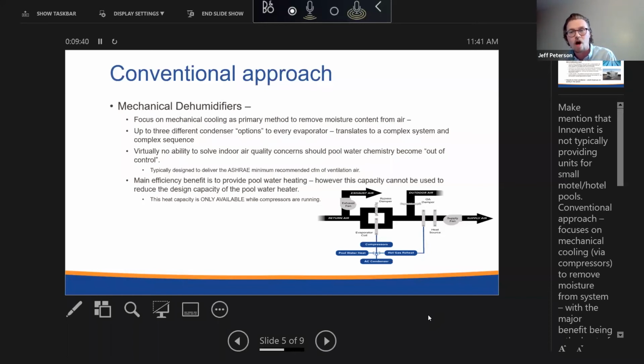The single biggest drawback to this approach, though, is it only allows for the minimum ASHRAE prescribed amount of outside air. So if you have a situation where chloramines build up in the space, and that's not something as an engineer you can design for, it's not something as a rep that Long can prevent, or as a manufacturer that we can really do anything about. If an owner doesn't maintain the pool water chemistry properly and they run into a problem with chloramines, these mechanical dehumidifiers do not have the ability to introduce enough outside air in an efficient manner to offset that issue and clear it out. They can go through a shocking procedure, but that's not something that you can do every day of the week or every week of the year. It's something you can only do once in a while. And so that's the major drawback to their approach.